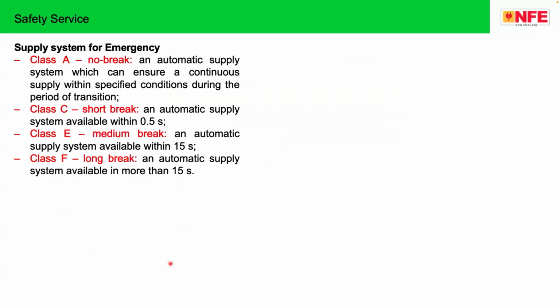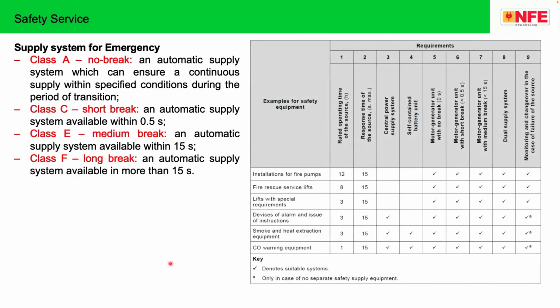Safety services are classified as Class A, Class C, Class E, and Class F. Class A means there is no break, there is a continuous power supply. Class C means there can be a break of up to 0.5 second. Class E, 15 seconds, and Class F more than 15 seconds. The application of these is very well again included in the respective standards. For example, installation of a fire pump: rated operating time is 12 hours, and the changeover response time is maximum 15 seconds.